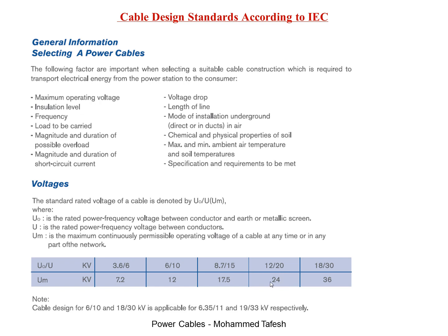24 is the value which the cable can bear, but if you apply 30 on the cable, this cable will be damaged immediately because it will break the insulation of the cable. Note: cable design for 6/10 and 18/30 kilovolt is applicable for 6.35/11 and 19/33 kilovolt respectively.